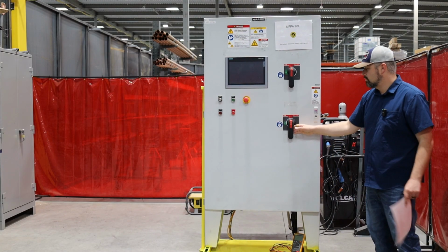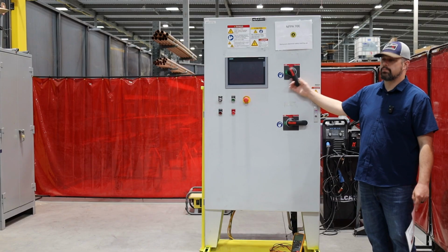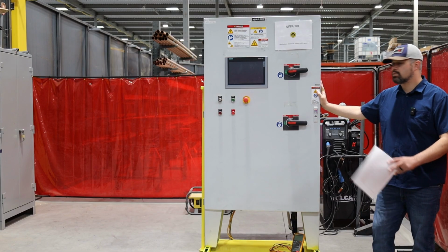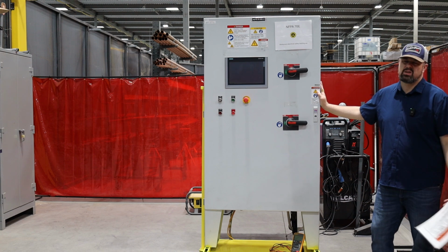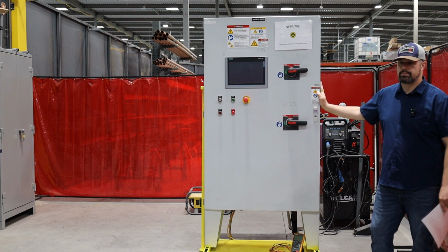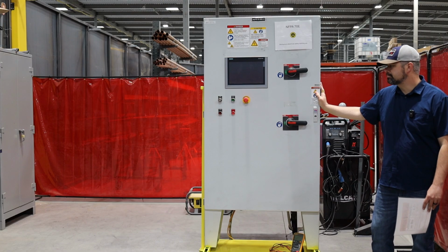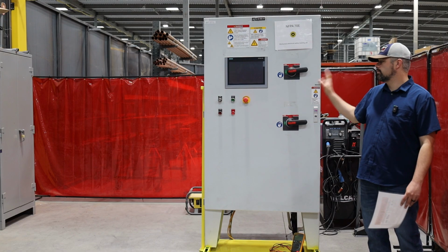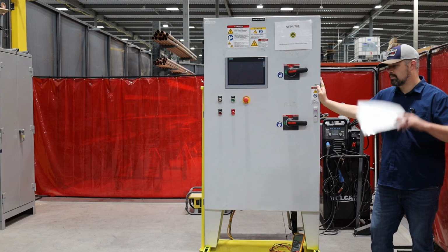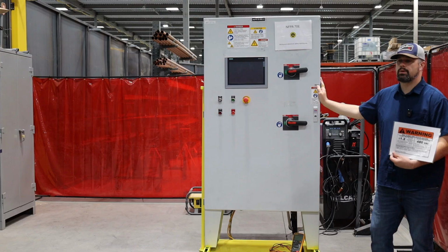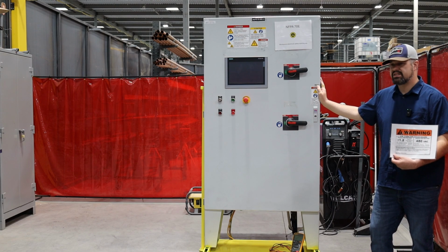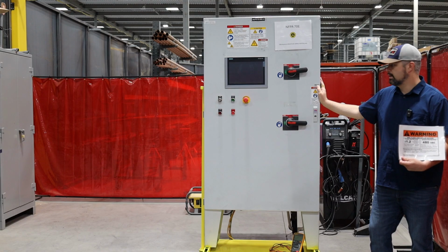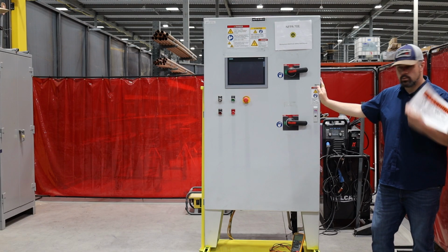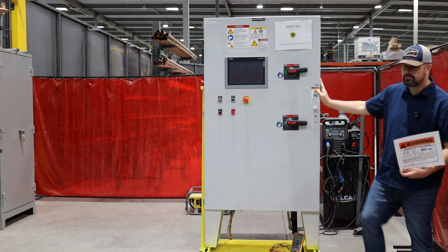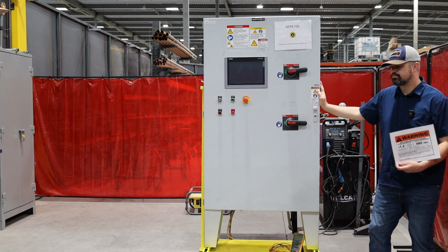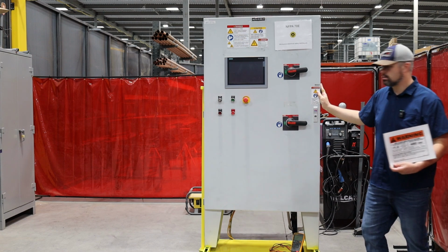Let's say that we've been tasked with shutting this entire panel down, okay, and basically verifying that it's dead. Maybe the controls tech is going to come in here and do some work. They're going to change out a breaker for maintenance. Okay, so we shut it off. We've got our boundary up, 42 inches. We've got all the PPE we need, 1.2 cal and below, to be within that 18 inches. Is it dead? No, the answer is no, right? Until we go in and verify it with our approved electrical testing device, our Fluke meter down here, we're not going to consider it dead. We're going to consider it still alive, okay?